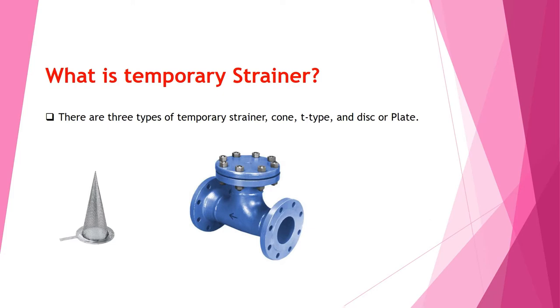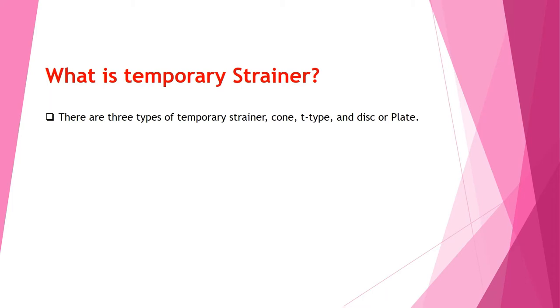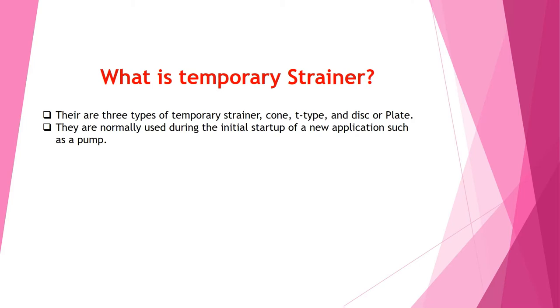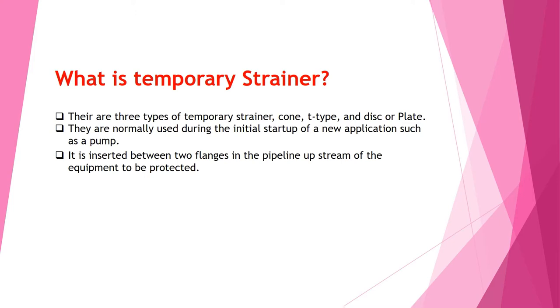There are three types of temporary strainer: cone, T-type, and disc or Plate. They are normally used during the initial startup of a new application such as a pump. It is inserted between two flanges in the pipeline upstream of the equipment to be protected.